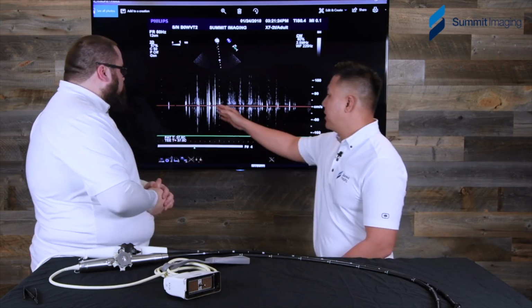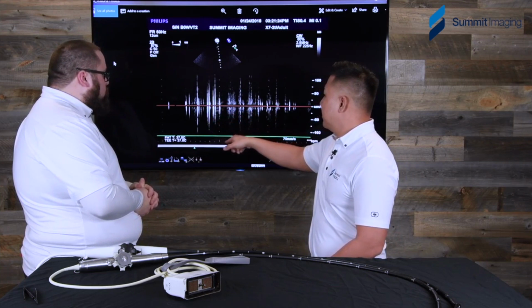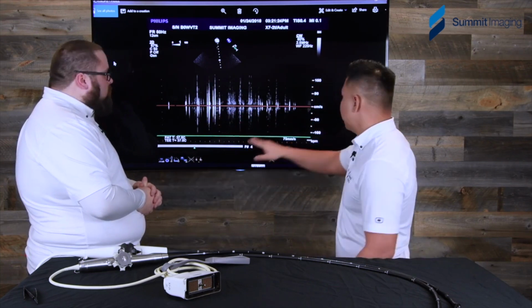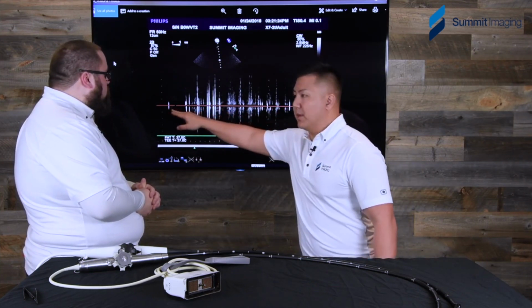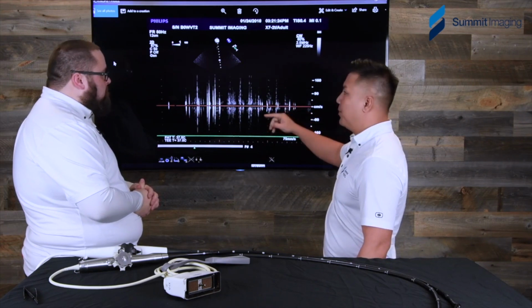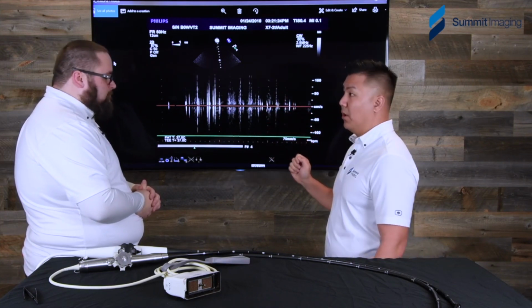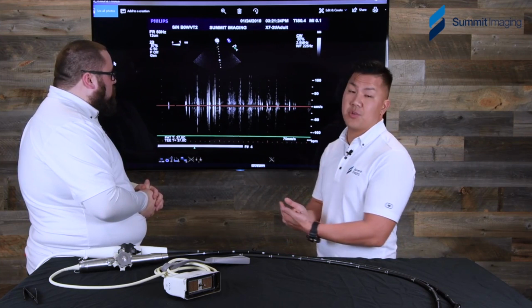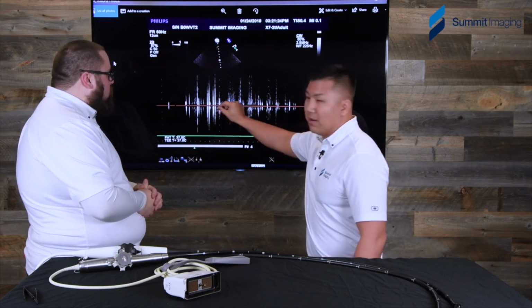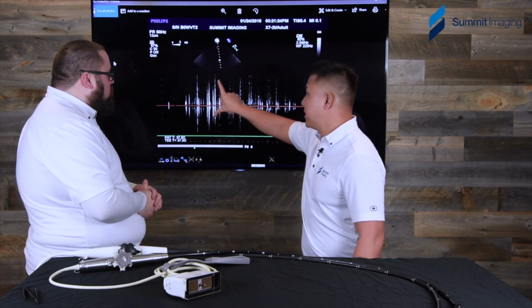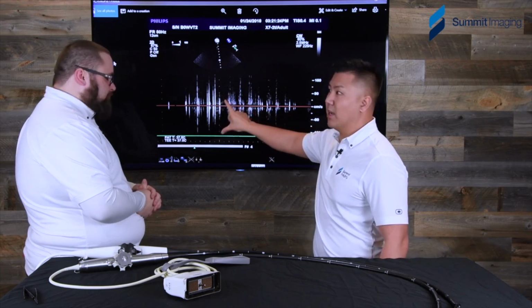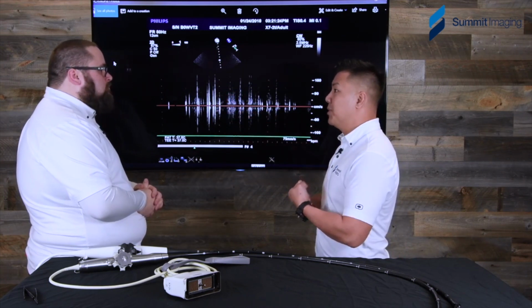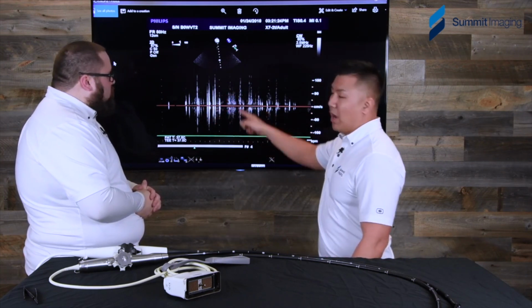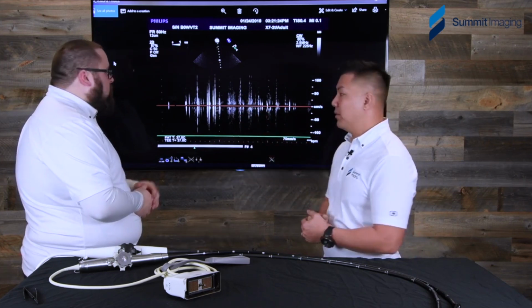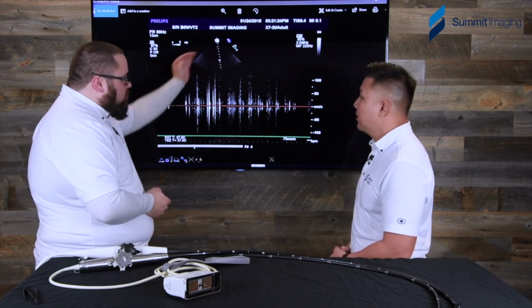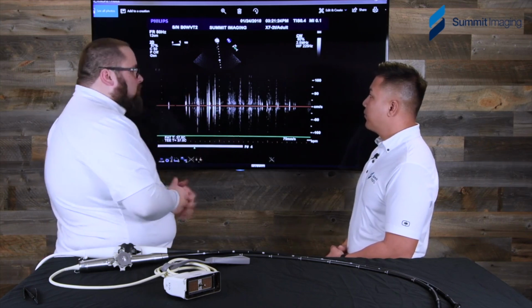On top of the spiking you see, it's also about basic image quality. Above this axis here and below means to and from the blood flow from the face of the transducer, and you can't have fluid going to and from at the same rate at the exact same time. It's just physically impossible. So you really don't get the proper waveforms of blood flow that they're looking for. It's a chatter instead of a waveform. You're just getting a spike.